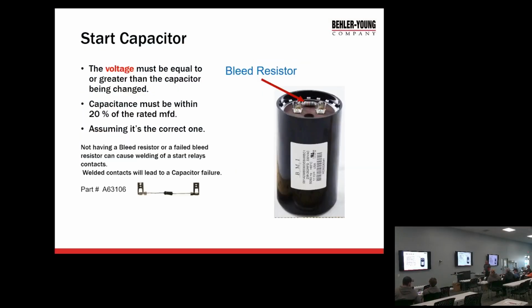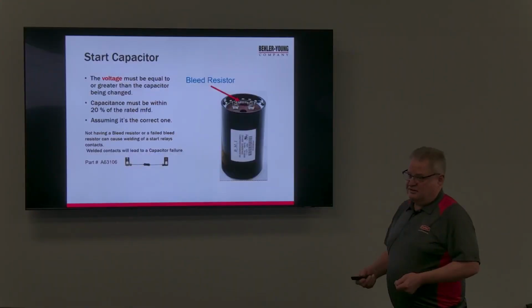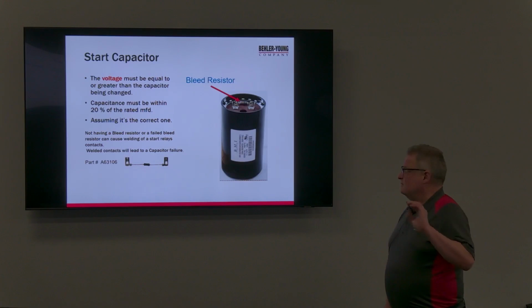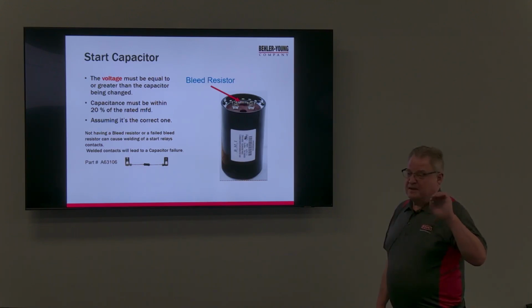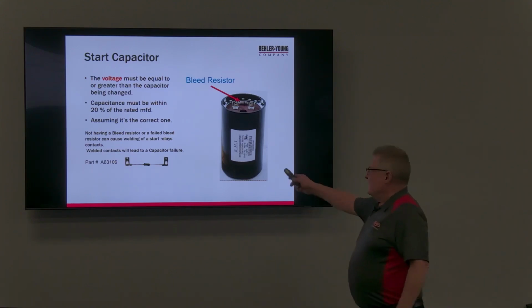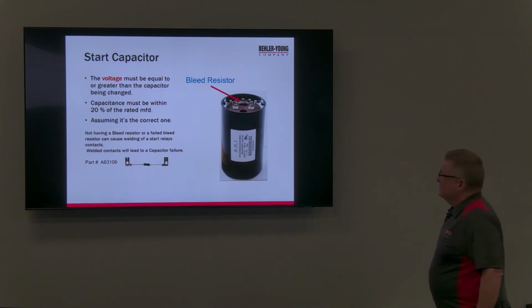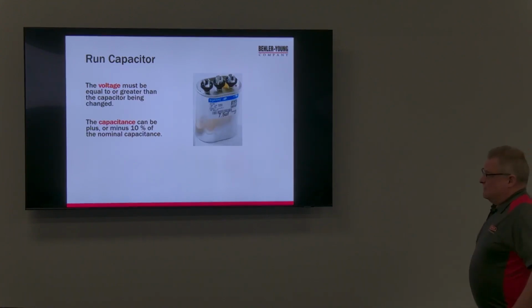Start capacitors, which normally we add on. We don't normally have them OEM, but we have aftermarkets we can add on. When we replace the start capacitors, power them down and make sure they're bled down. Most of our meters have microfarads on them, which is that funny looking uF symbol. You just read it across the top. Plus or minus 10% for run, and they say 20% for start, plus or minus 10% of the rating on it. Take the bleed resistor off first. The runs are plus or minus 10%, same thing.